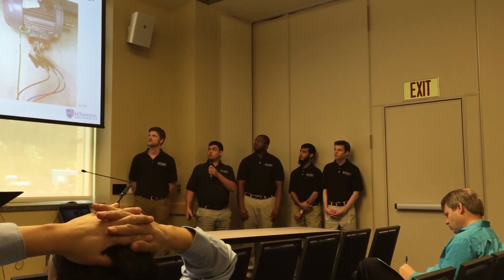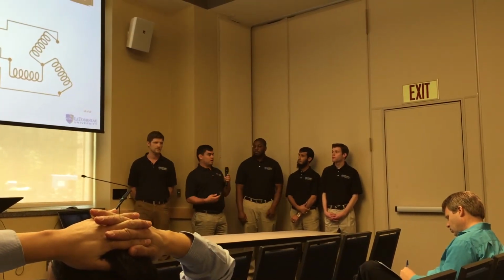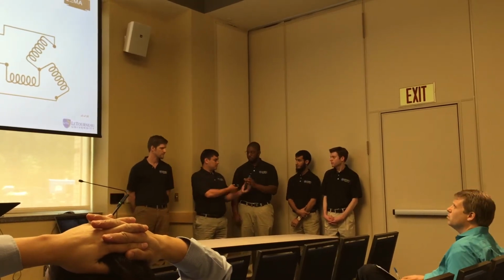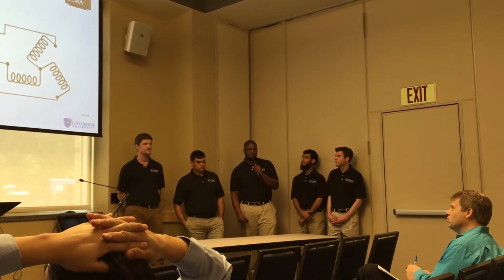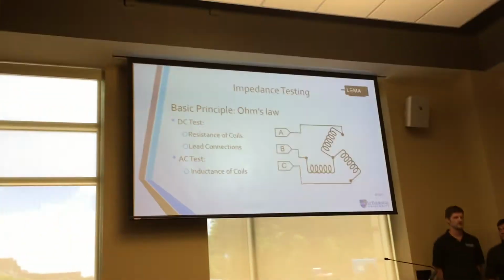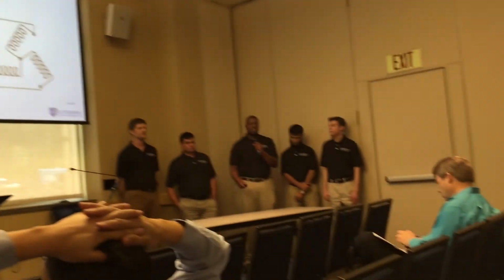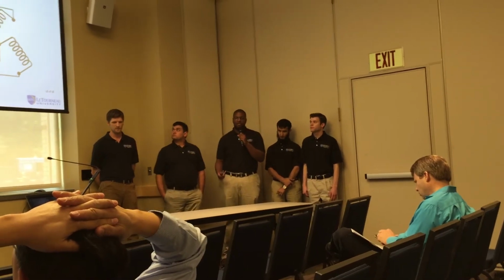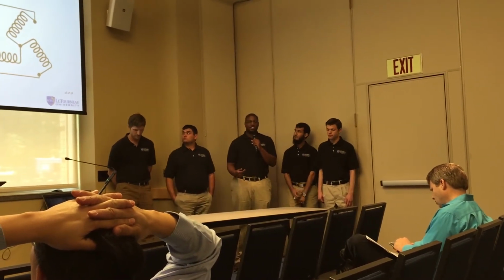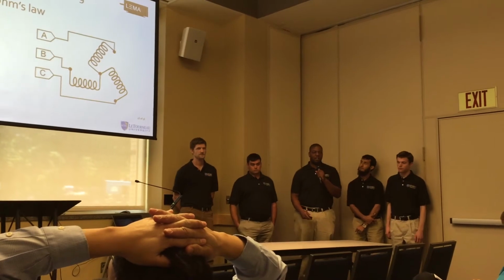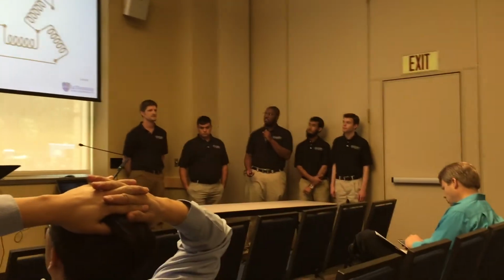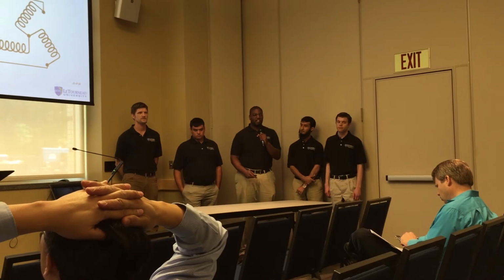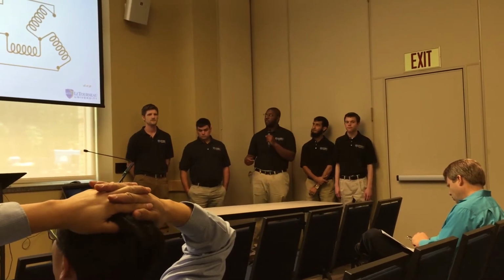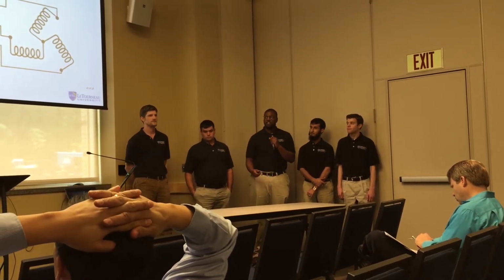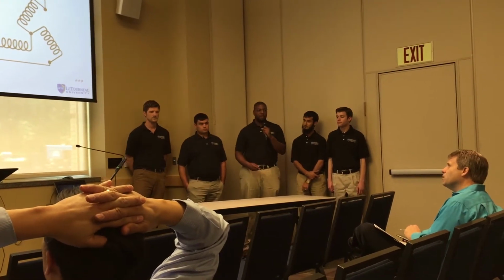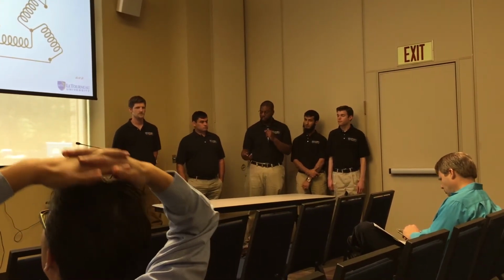After that test, we move into impedance testing, and I'll let Logan talk about that. To find the impedance of the motor, we have two different tests. We have a DC test, which applies DC voltage to the motor, and from that we calculate the actual resistance of the copper inside the windings. Then we have an AC test, which we use to calculate the inductance of a set of windings. We then compare the different sets inside the motor to each other to come up with an imbalance measurement for that motor.